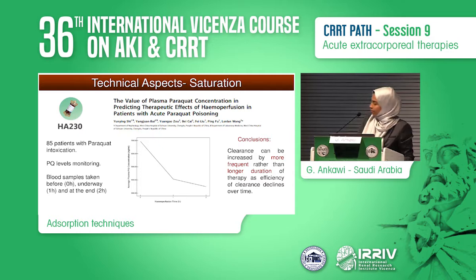What they noted is the most clearance you get is within the first hour of therapy. Beyond 1 hour, clearance dramatically drops. So in other words, if you're trying to get effective clearance by adsorption, you want to think about more frequent therapy rather than prolonging your session of therapy. This way you're getting another peak.